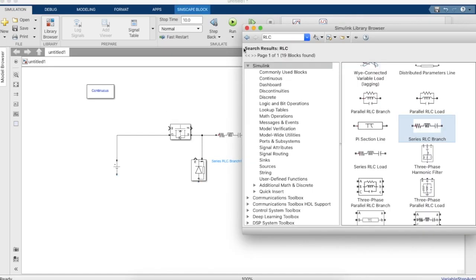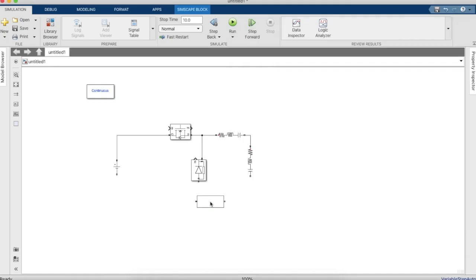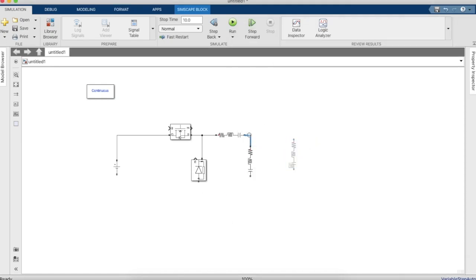Whereas the load you will have to specify in terms of watts. So our load will be a resistive, purely resistive load and as mentioned in the design section we will keep it at 500 watts.